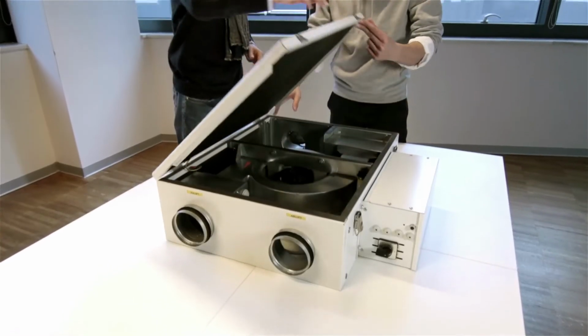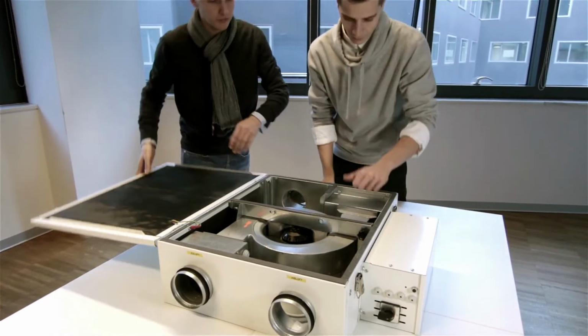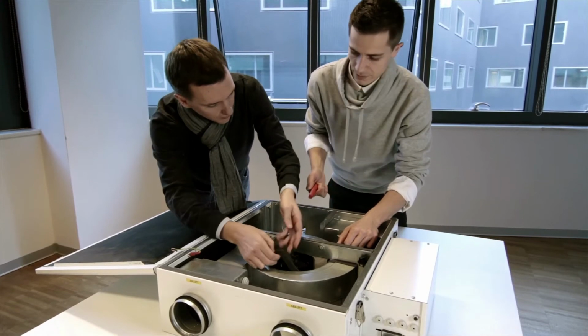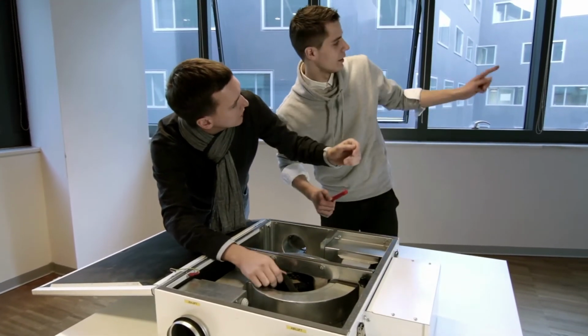The ventilating fans and the heat exchanger are usually located in the basement of the building and require a widely ramified air duct system. This obviously makes these kinds of systems problematical for installation in existing building stock. Although there are already some compact devices for retrofit installation on the market, they have only limited efficiency.